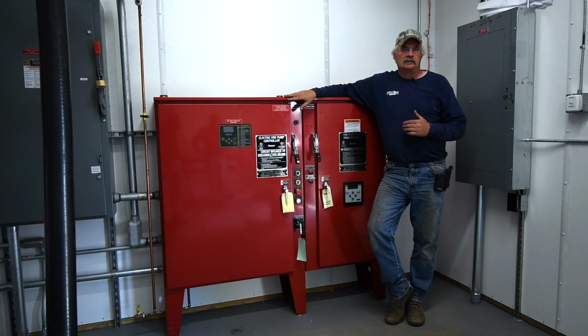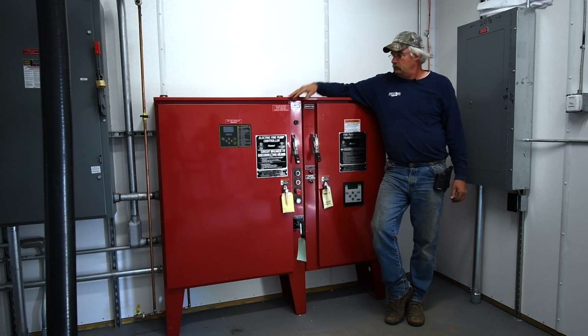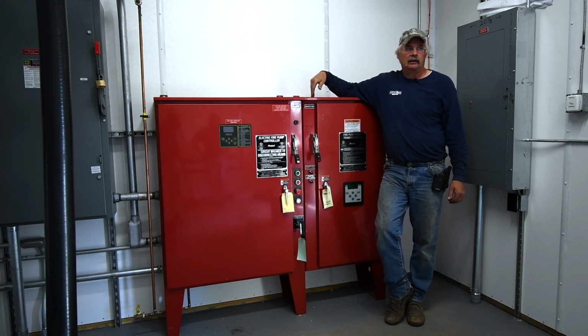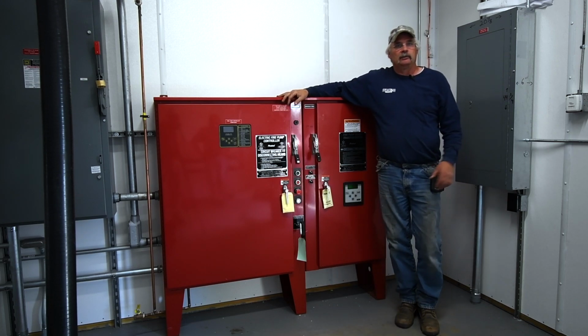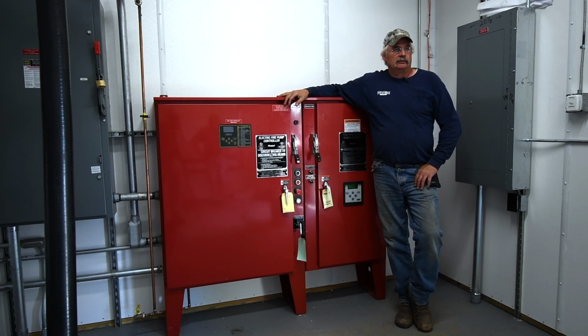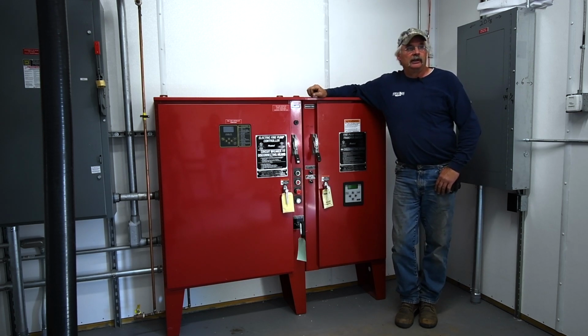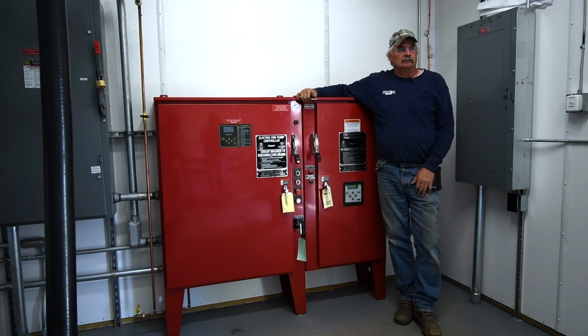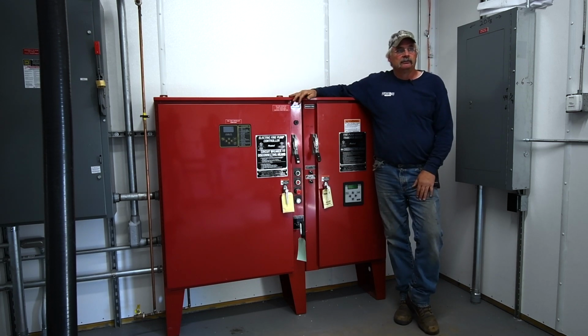The reason for the diesel backup is because of the location of the facility and the distance between here and the local fire department. If they were closer to the facility, you wouldn't need a diesel backup, because the fire department could respond in a timely fashion. Right here, it's a volunteer fire department, and it's based on who's available. So to take that factor away, because of not just this new facility, the existing school, the existing bus garage, the existing shop, the existing gymnasium, all of that is run off of this fire pump.